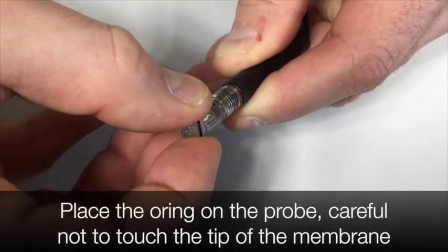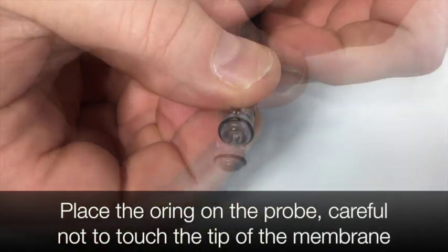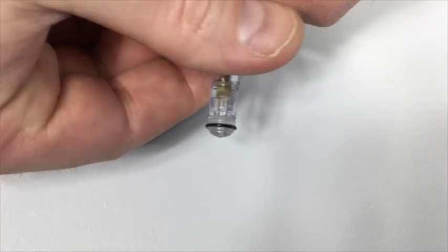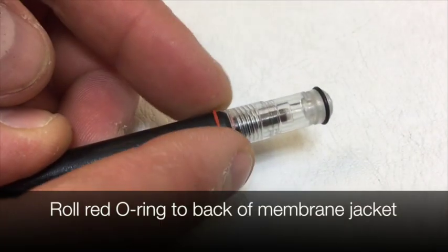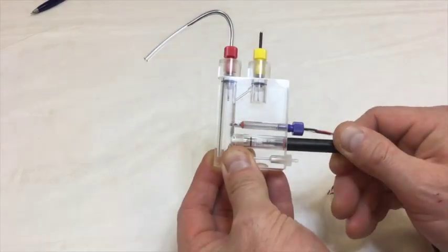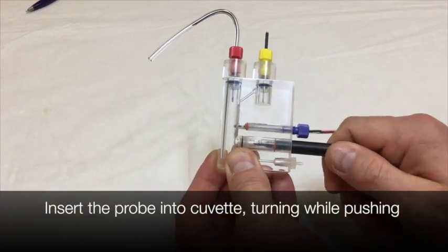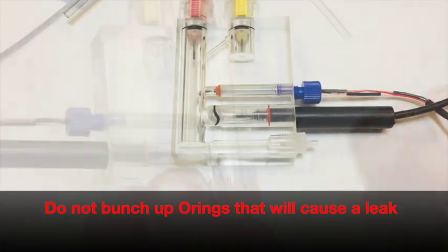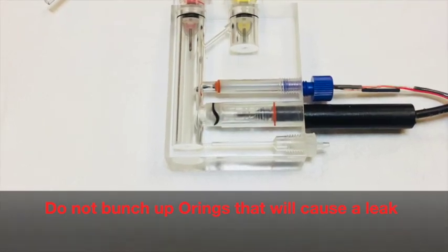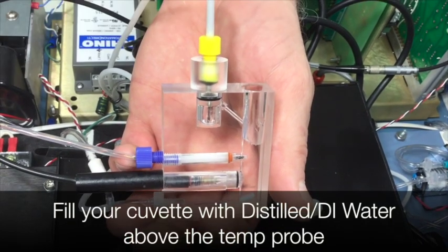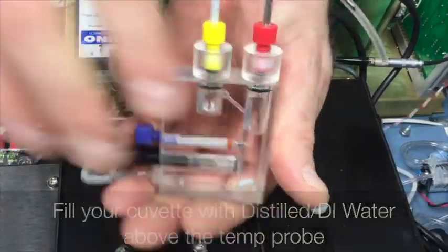Place the black O-ring around the tip of the membrane jacket, making sure not to touch the membrane with your fingertips. Roll the red silicone O-ring forward until it gets into the groove of the back of the silicone jacket. Insert the probe into your cuvette, making sure you turn slowly as you push it in. Make sure that you do not bunch up the O-rings. That will cause a leak. Fill your cuvette with distilled water above the temperature probe. Put the cuvette back in the HEMOX.